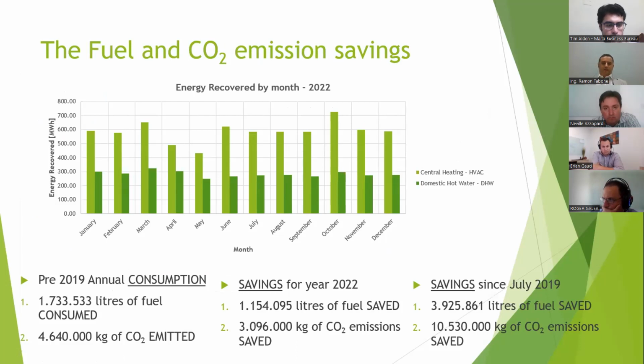So I took the latest data for a whole year, which is 2022. As you can see, the dark green is the energy recovered for the domestic hot water. As I said, we're not using any fuel there for the domestic hot water because the demand is covered only by the heat recovery of the chillers.